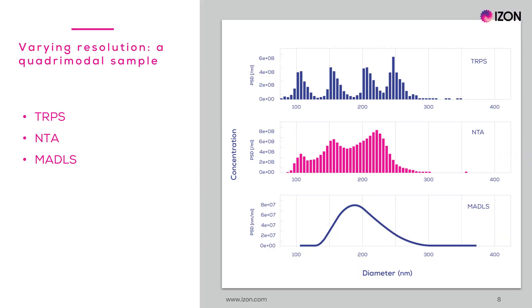This figure shows the concentration of particles plotted against particle diameter. TRPS data is shown at the top, with four clearly defined subpopulations. NTA data is in the middle, where only three subpopulations were detected with poor resolution. At the bottom, MADLS shows no evidence of the four subpopulations in the sample.